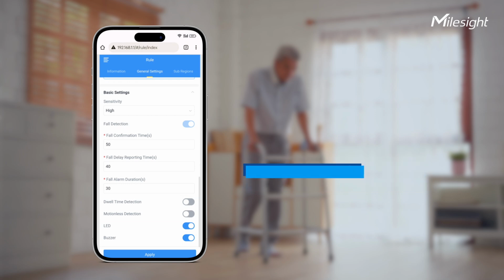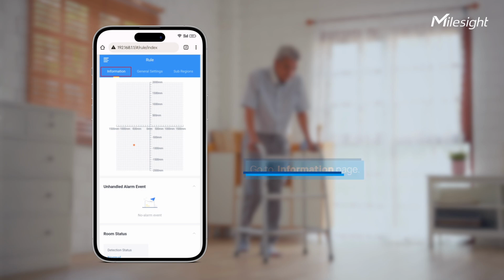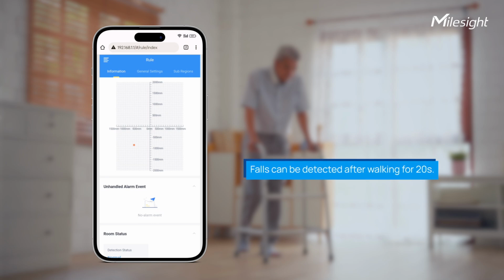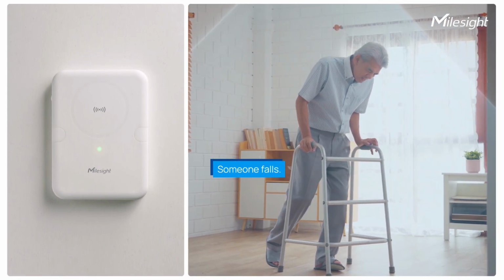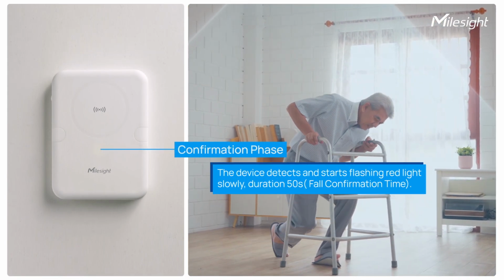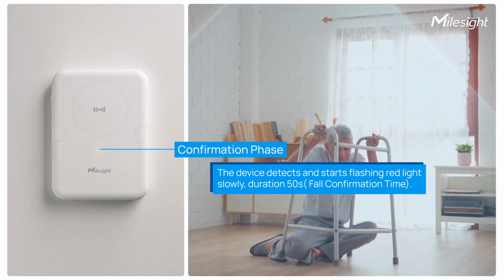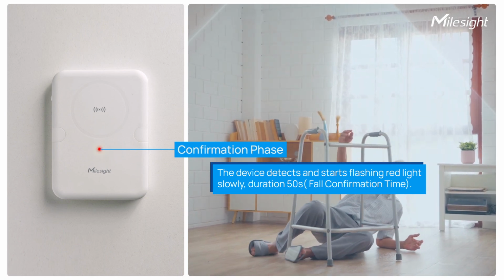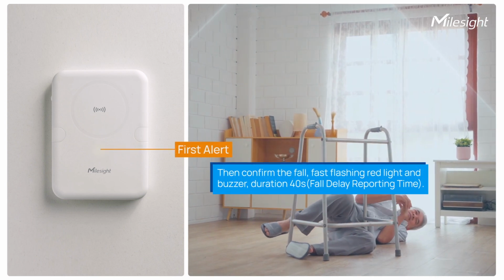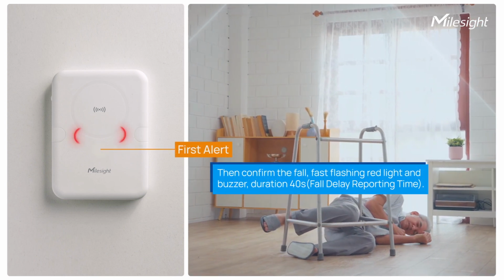Click Apply. Go to Information page. See the target point. Falls can be detected after walking for 20 seconds. Someone falls. The device detects and starts flashing red light slowly. Duration 50 seconds. Fall confirmation time. Then confirm the fall. Fast flashing red light and buzzer.